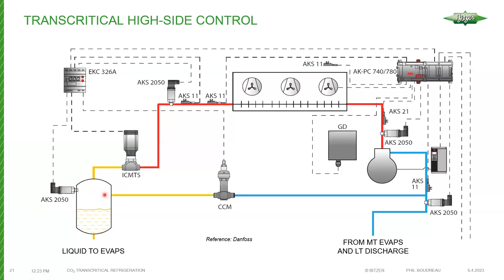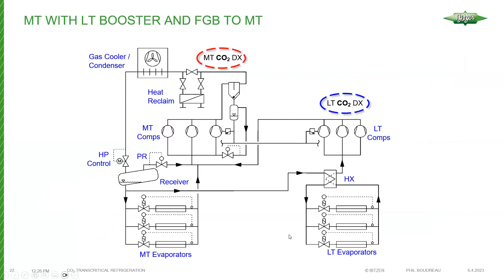We're forming a lot of flash gas when operating in transcritical mode, and we don't want to send that to the evaporators. There's a pressure transducer connected to the receiver on the vapor side with a predetermined setpoint pressure — perhaps 500 to 600 PSI. As pressure begins to exceed that level, a controller opens what's called a flash gas bypass valve, taking vapor off the receiver and transferring it directly into the medium-temp compressors.